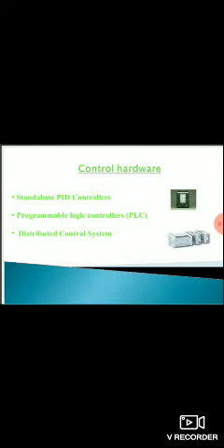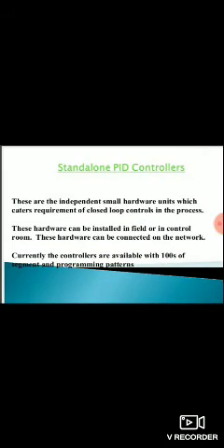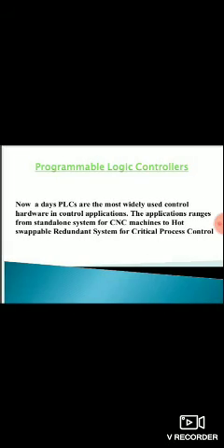Control hardware: standalone PID controllers, programmable logic controllers, distributed control system. Standalone PID controller: these are independent small hardware units which cater to the requirement of closed loop control in the process. These hardware units can be installed in the field or in the control room. They can be connected on the network. Currently, the controllers are available with hundreds of segments and programming patterns.